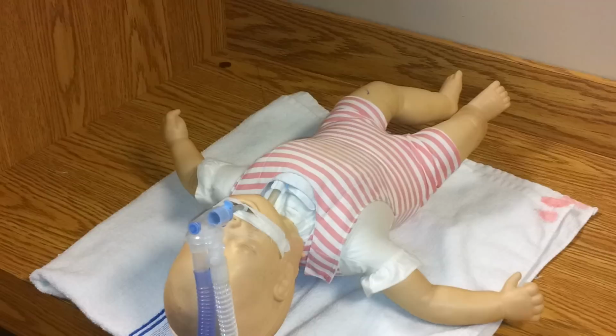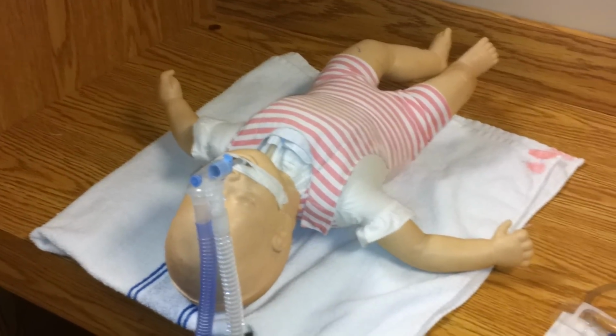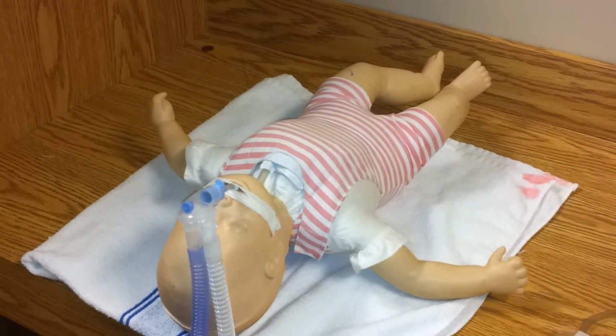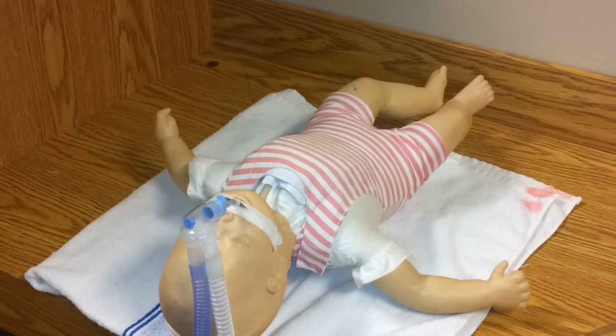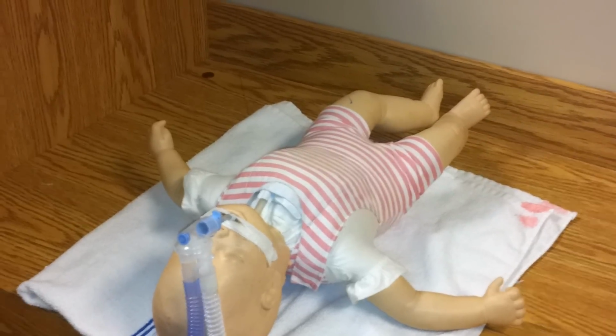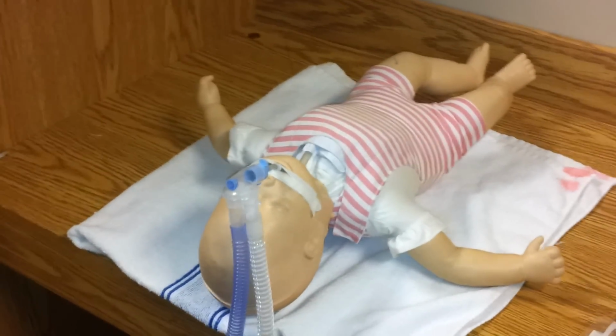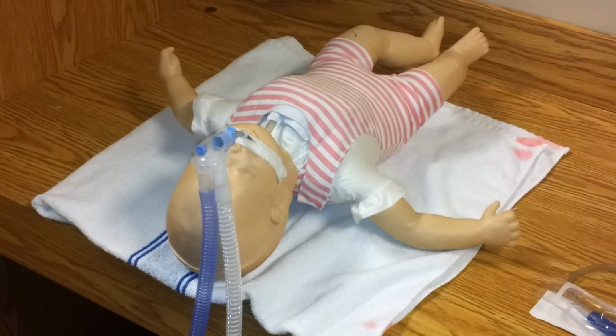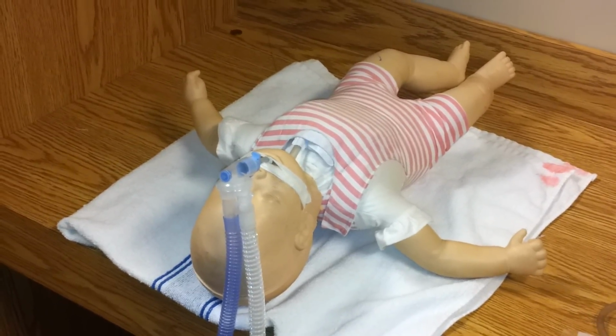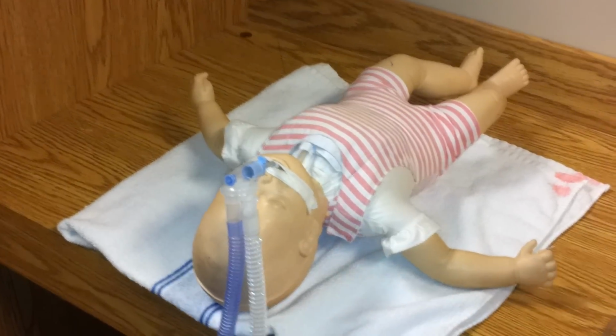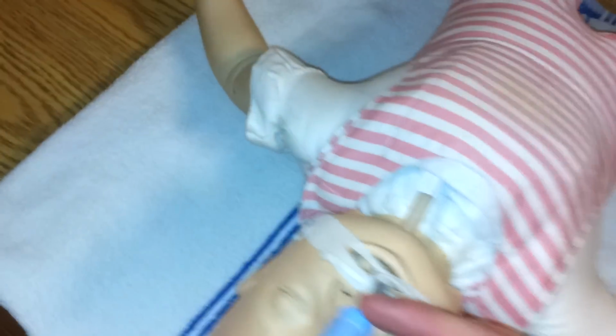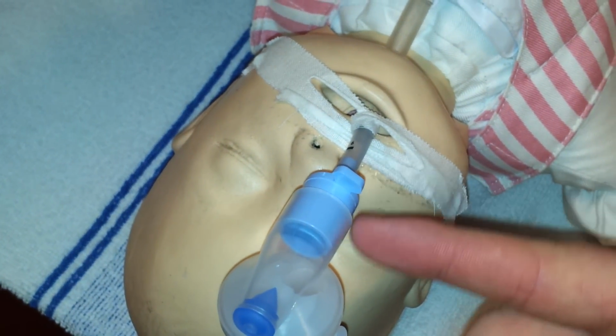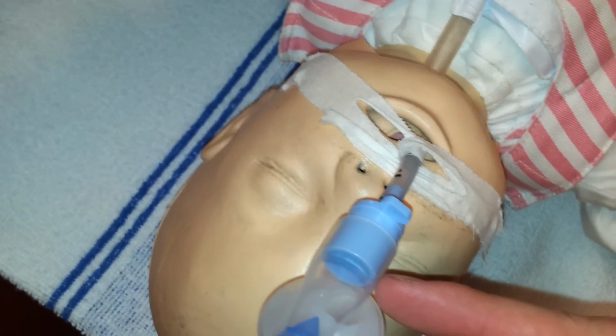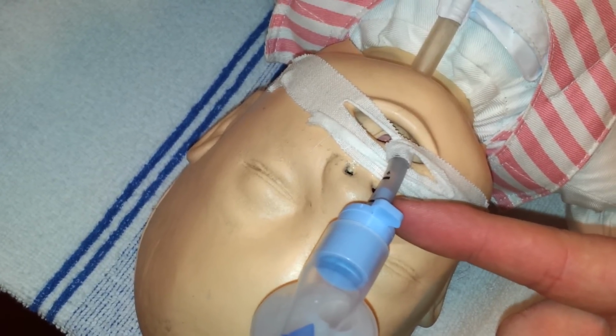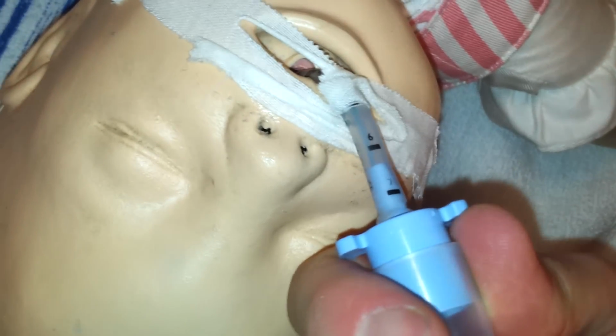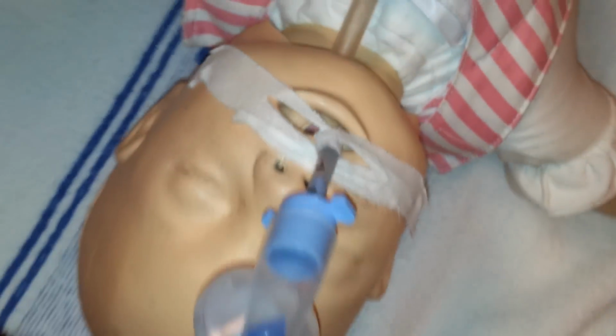Okay. So when you go to insert the catheter, you want to make sure that you're going to the correct depth. In a baby, what you want to do is insert the catheter to the end of the endotracheal tube, not until you feel resistance. So to calculate that, for open suction, you will use the formula length of the ETT plus 3 centimeters. The plus 3 centimeters is for the blue connector on the ETT. 3 centimeters is from the tip to the other tip. So on this one it would be about 6.5 plus 3 centimeters for suctioning depth.